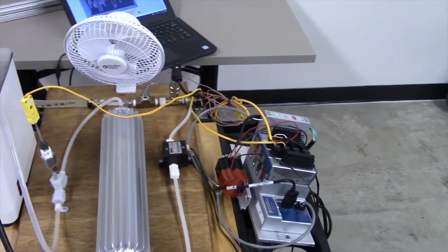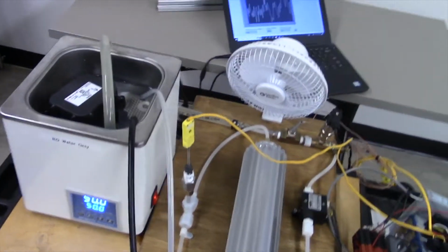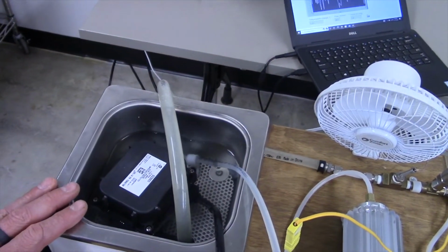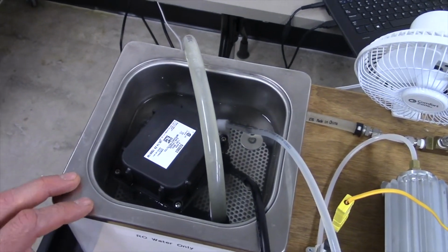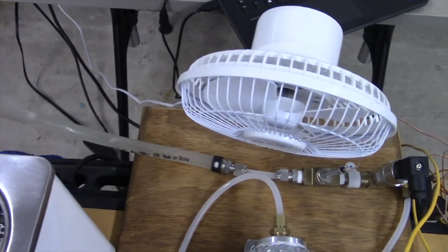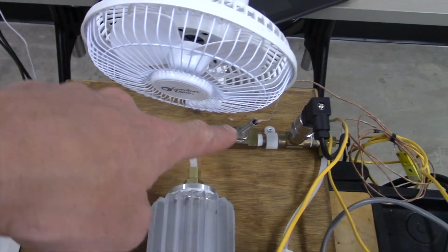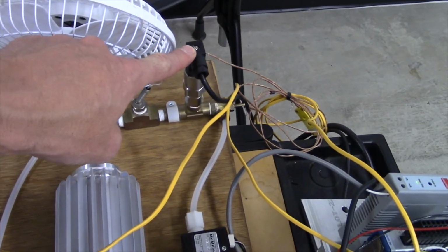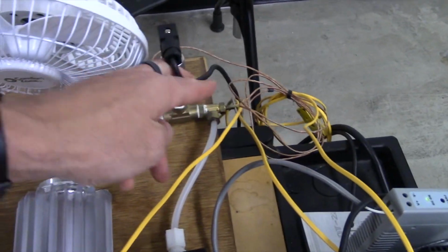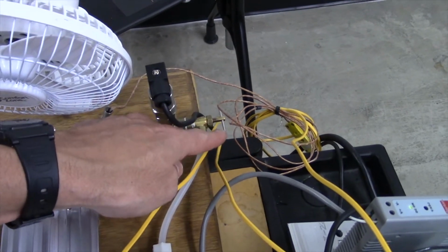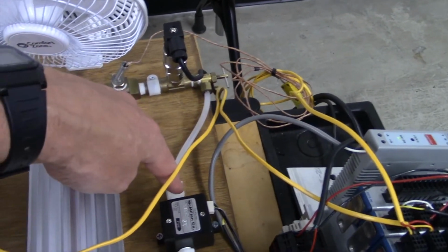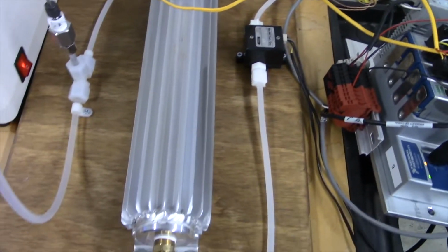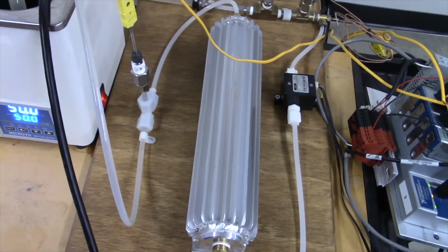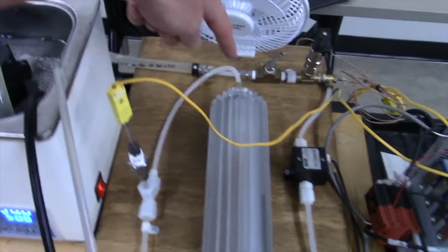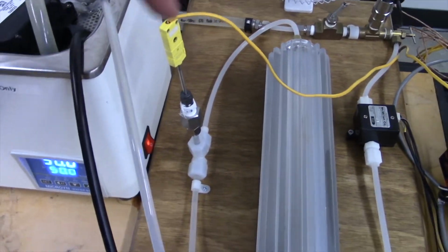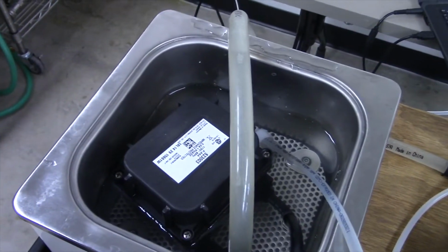Here's our DAQ unit that collects our data, and I'll just trace the fluid flow for you. Out of the heater, or the heated tank, our reservoir here, it comes around this tube, then goes through and it measures the temperature right there. Then the pressure is measured and transmitted. That's a little pressure sensor. And then there's a needle valve. Here you can see it where you can control the amount of flow by closing or opening that valve. And then the flow comes through this flow meter and then enters the exchanger. It's a little finned exchanger. And then the flow exits, and the temperature is measured on the exit, and then it flows back into our reservoir.